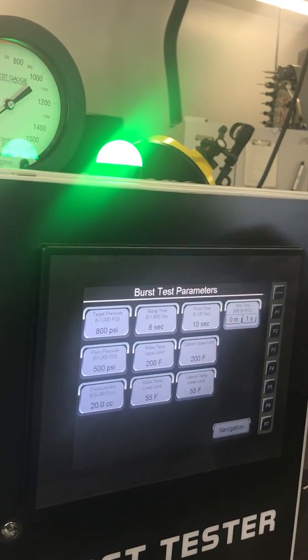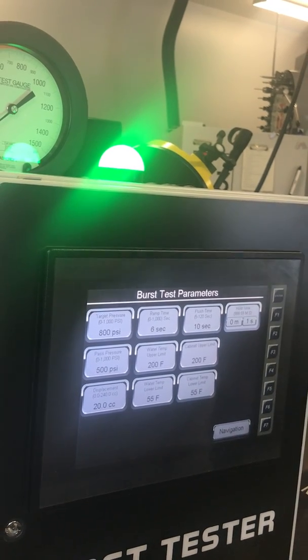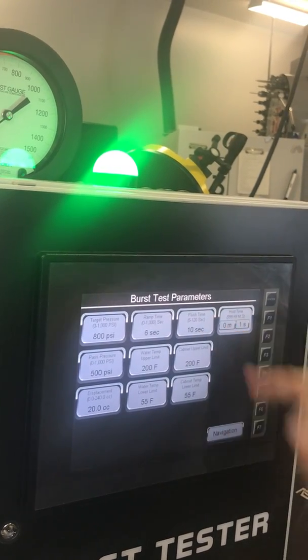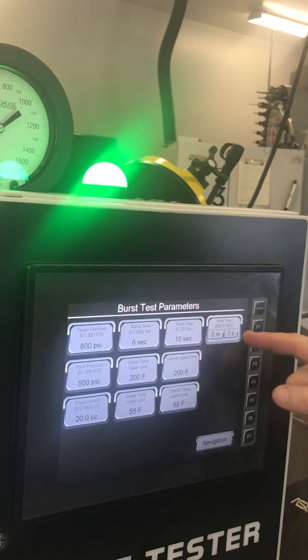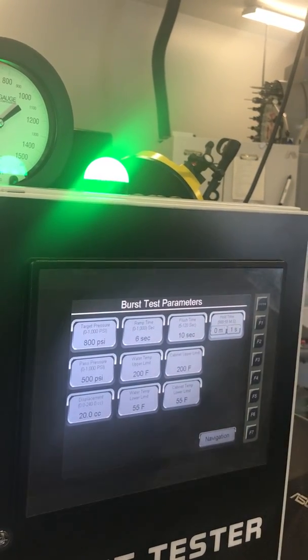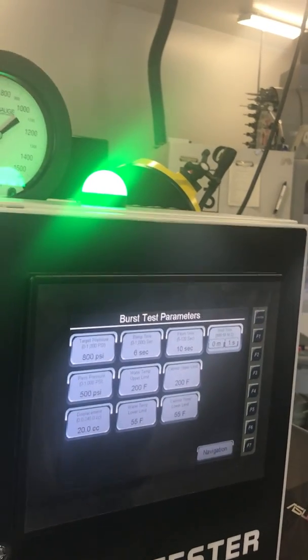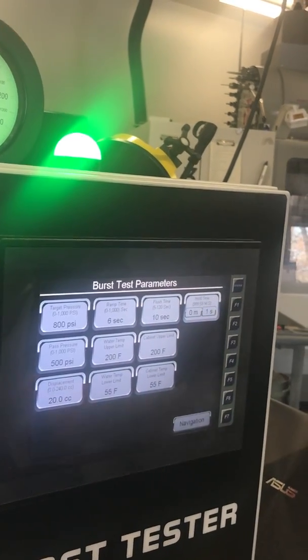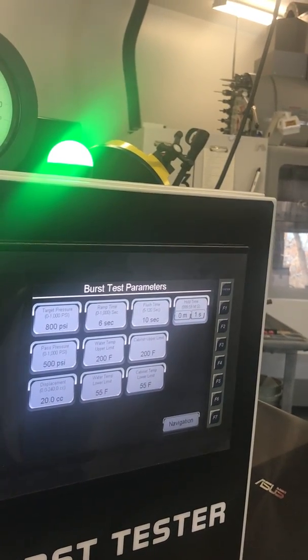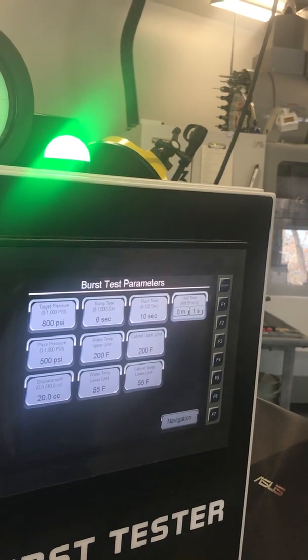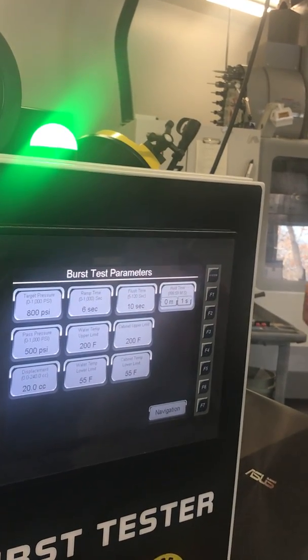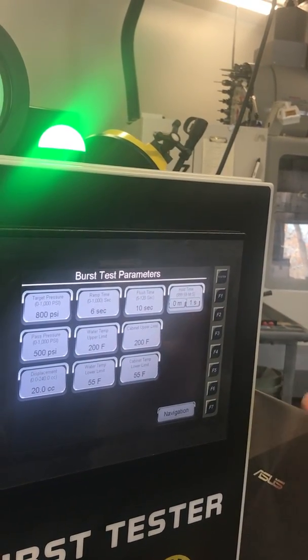Flush time, it's going to open the inlet and the outlet valve to flush any air out. For this, between 5 to 120 seconds. The hold time, well, on a burst test, you're probably not going to hold it. We've got 1 second. Go up to 800 and then come right back down. I tried to emulate this. I did a static test first, and it's almost identical to a static test.